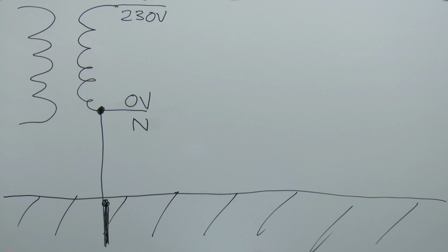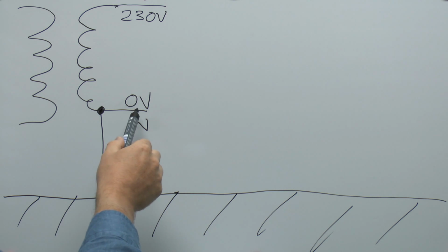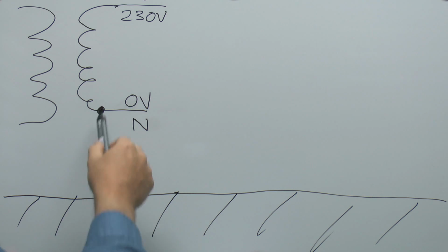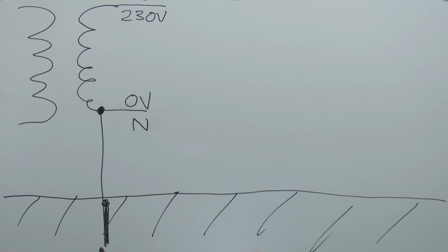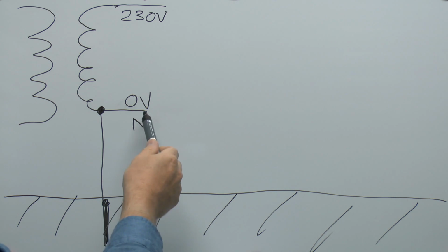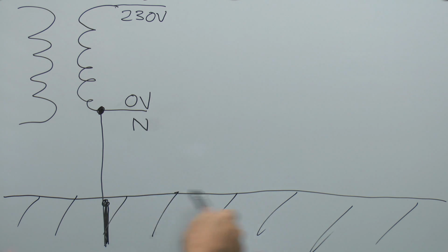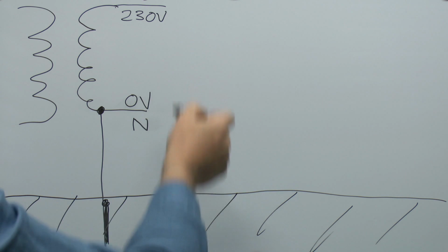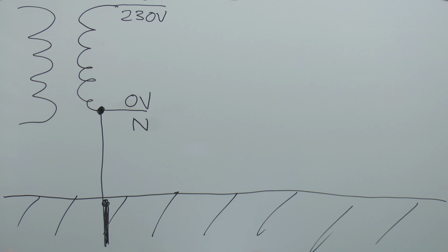And this means that you've got the neutral here and the earth effectively connected together, usually at the transformer and in some cases other places, so the voltage between the two is effectively going to be 0. They're both going to be at the same potential throughout the rest of the system, and the 230 volts can then be referenced either to the neutral or to the earth or ground as well.